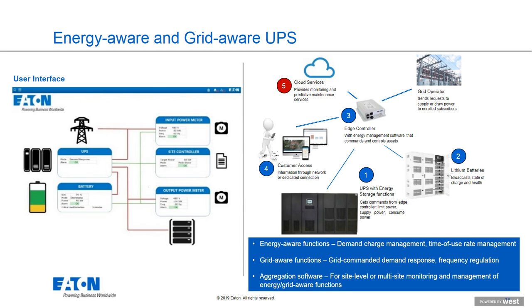On the next slide, on the left, we see an example of the user interface you'd see as the owner of the UPS. You'd see the UPS has demand response enabled, an on-off switch you'd select, and the capacity of the battery. The bottom of the battery shows yellow—that's the capacity reserved and dedicated for data center support. The green part of that battery icon is what would be available for programs like distributed energy resources, grid regulation, frequency regulation, etc.